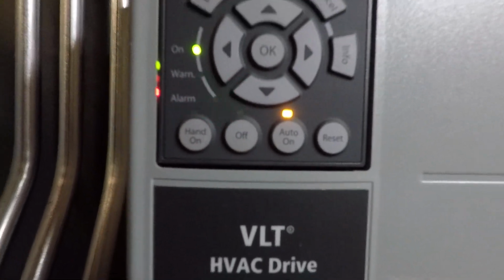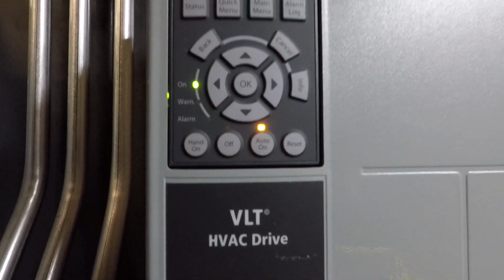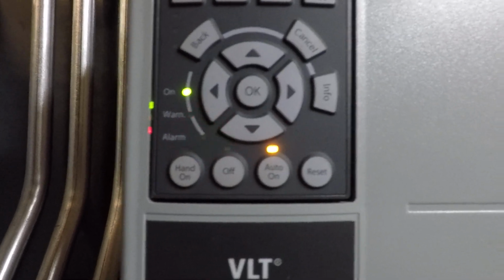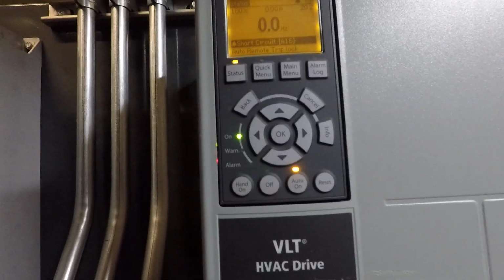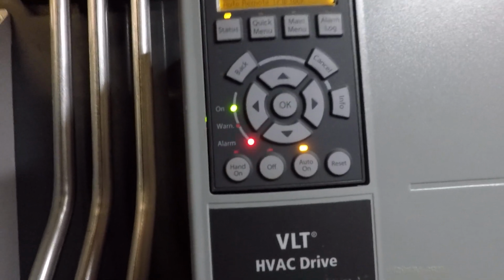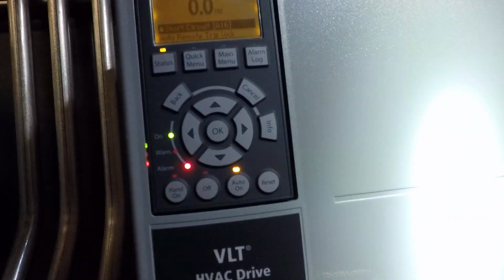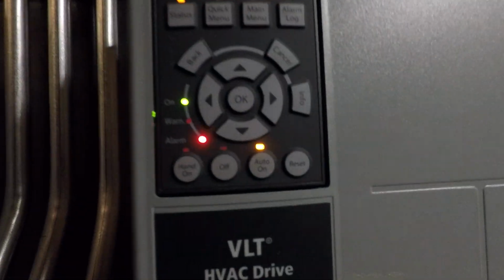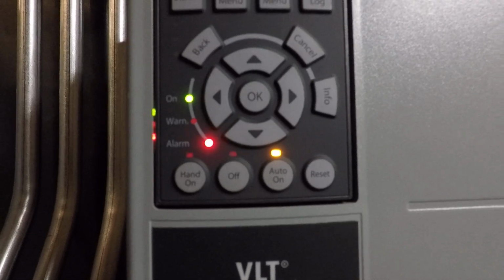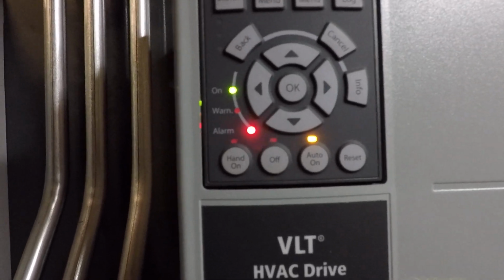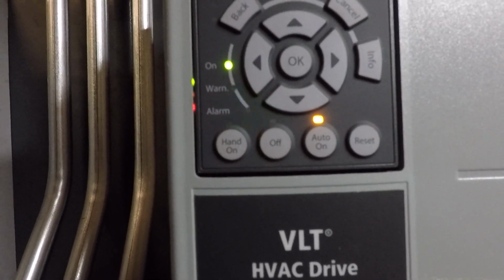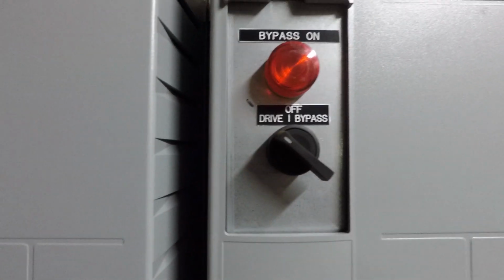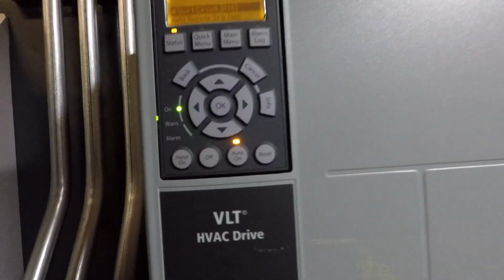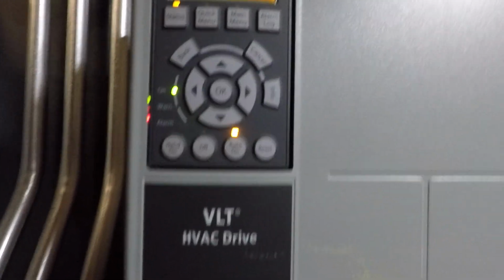The other control with this is, let me see if I can focus here. It has a hand on switch and an auto on. I don't know if that's going to work there. So to turn the drive on, you put it in auto, and you have the switch in drive, and then you're waiting for a DDC. And then you will get a DDC speed signal.